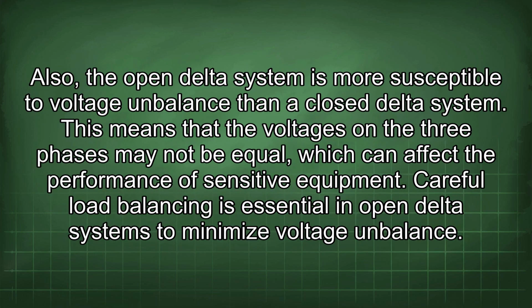Also, the open delta system is more susceptible to voltage imbalance than a closed delta system. This means that the voltages on the 3 phases may not be equal, which can affect the performance of sensitive equipment. Careful load balancing is essential in open delta systems to minimize voltage imbalance.